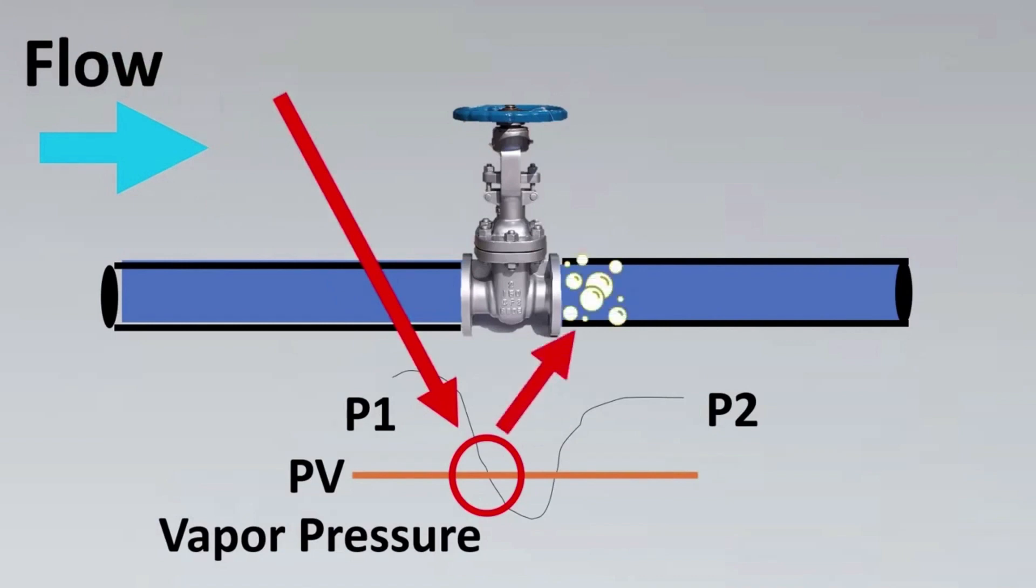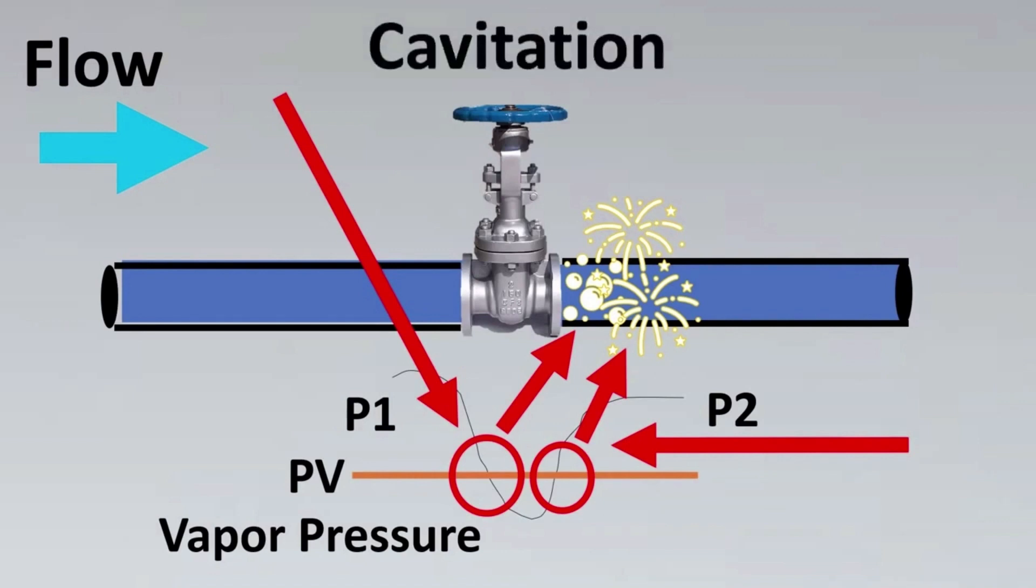At the exact opposite side, the vapor is going to turn back into liquid state. What happens here is the bubbles are going to burst to come back to liquid state, which is called popping. This has very high velocities that can damage the valve and the piping downstream. This entire phenomenon is called cavitation.